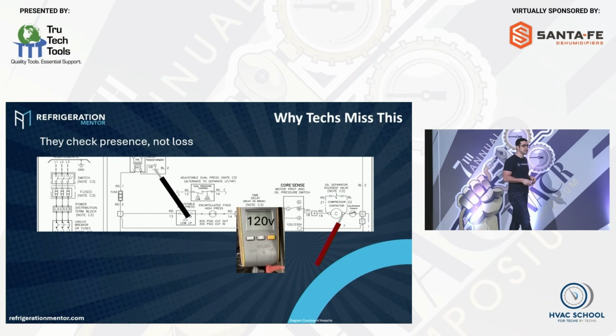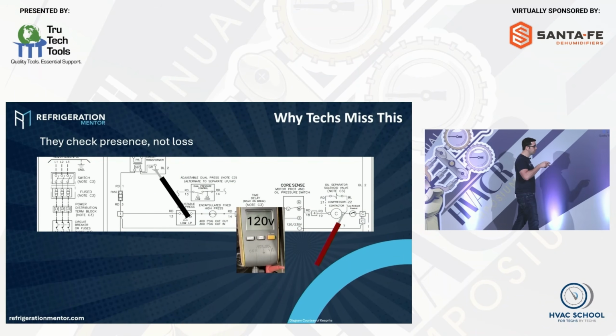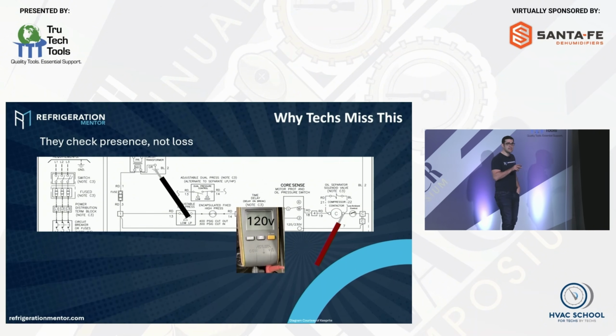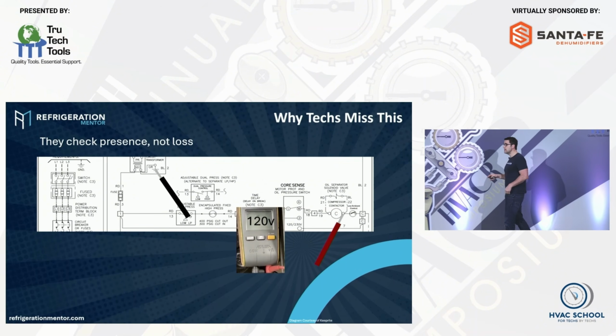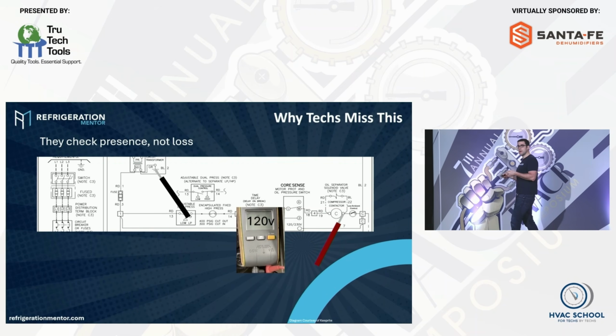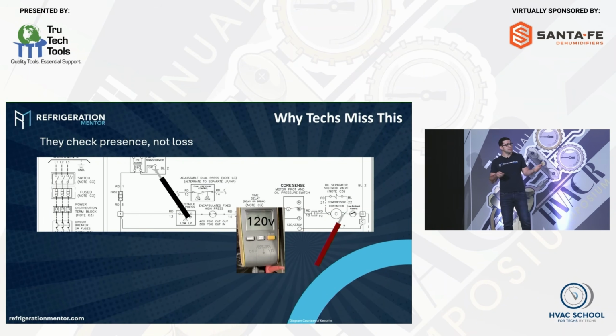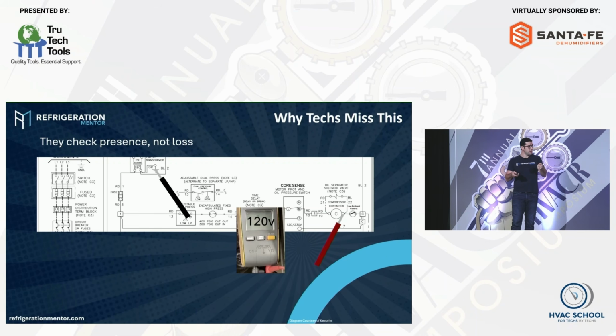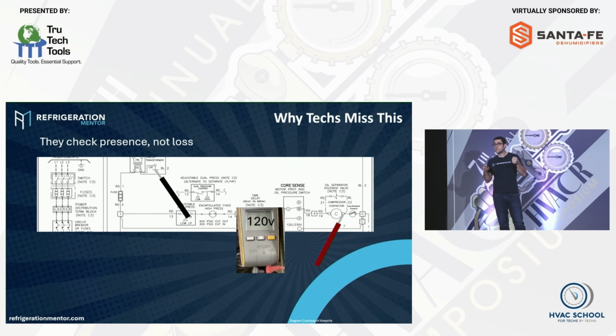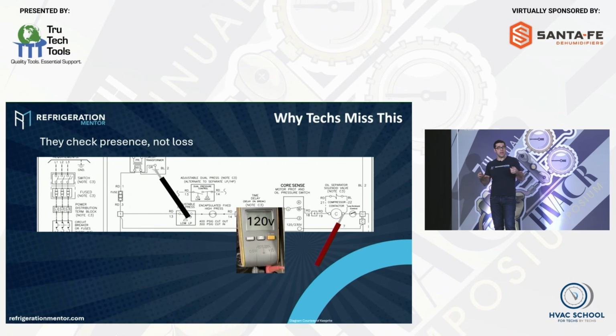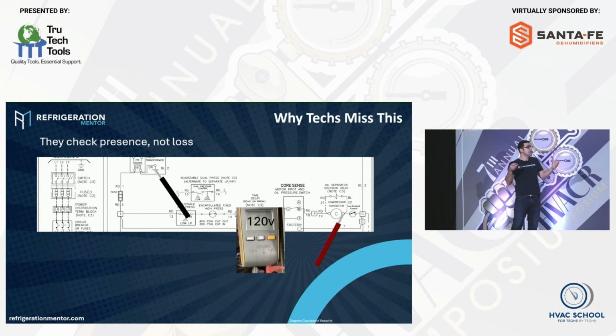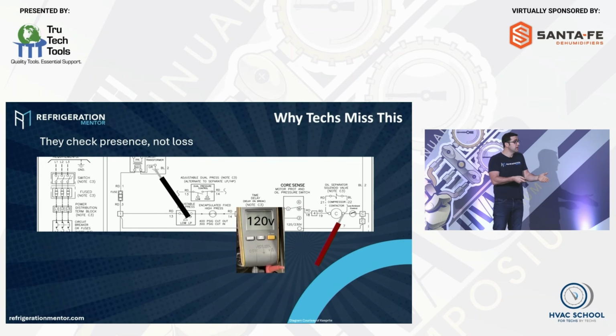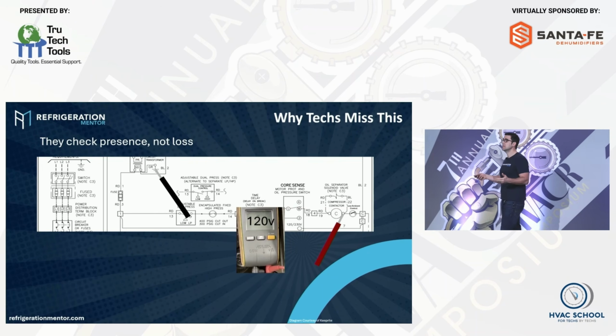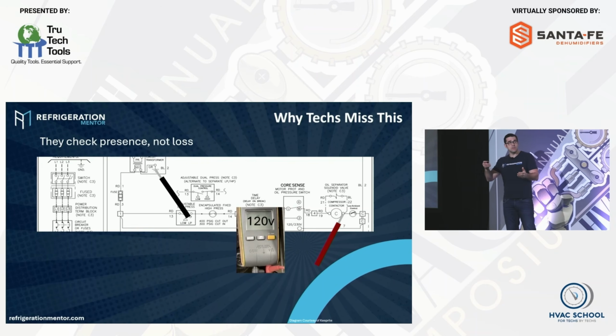Why techs miss this? Here's a really good one. They check presence, not loss. Here's a really good example that tripped me up multiple times in the field. I went up to a coil on a contactor, and I'm thinking the contactor should be pulled in. I got 24 volts. This is an example. I got 120 volts before the coil to ground. I got 120 volts after to ground. Well, what does that really mean? I go across, I got 0 volts. I'm thinking, oh man, this should be pulled in. I'm getting voltage to it, but it's not pulled in. What does that mean? Well, that means something downstream of it is open.